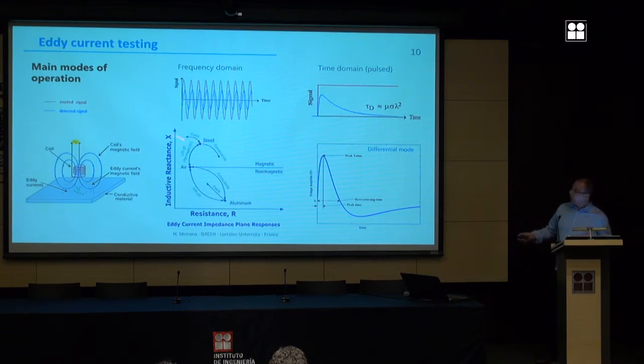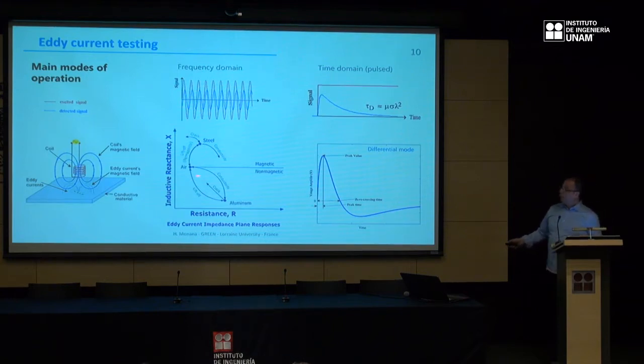The presence of a crack will induce a variation in this direction, and the presence of conductivity will lead to a diminution of the reactance, because the eddy currents will oppose the source magnetic field, and then the reduction of the coil. So we go down here. If the tested material is conductive, we go here. For example, here the response for aluminum.